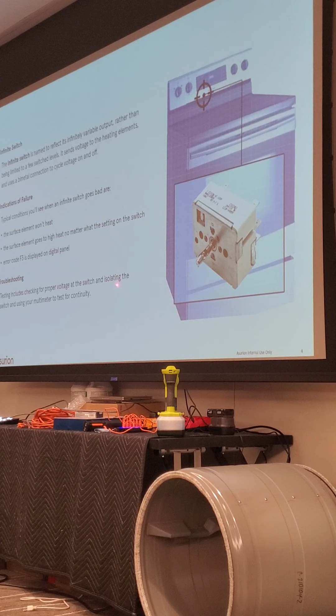Testing includes checking the proper voltage to the switch, isolating the switch, and using the multimeter to test the continuity and ohms on those, okay? How much voltage goes to the infinite switch? 240 volts. You've got L1 and L2 going to it, you'll need 240 volts. When you're in the customer's home, you're only going to get anywhere from 204 to 208.